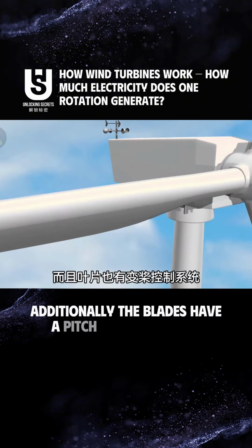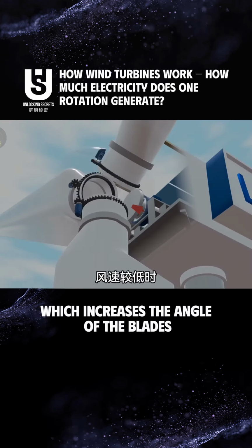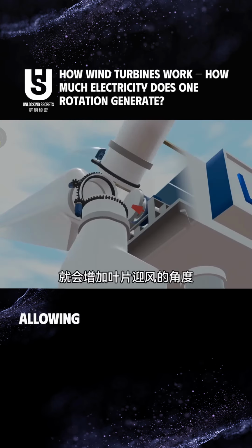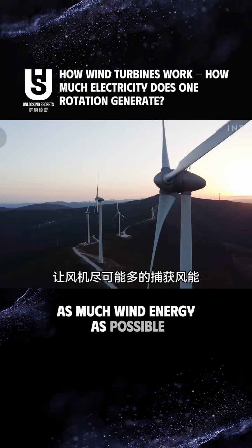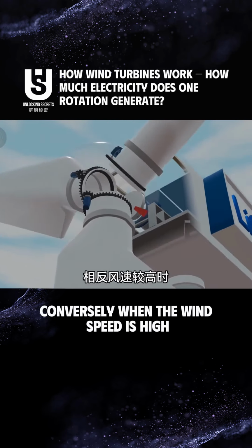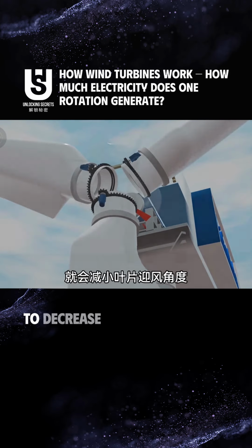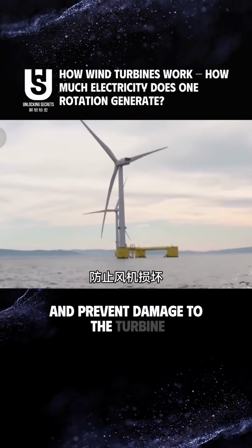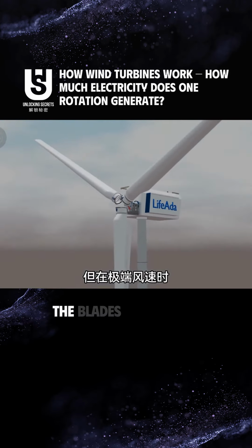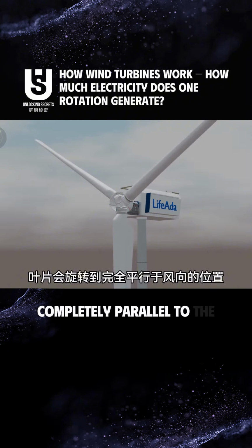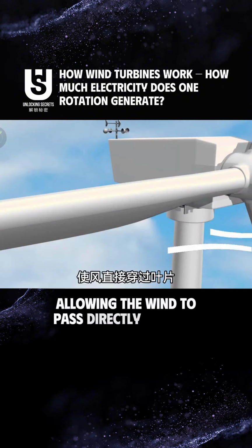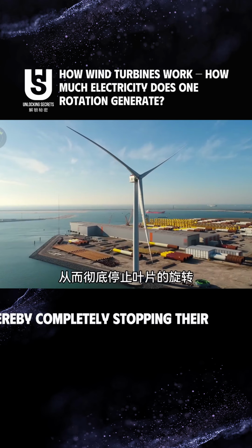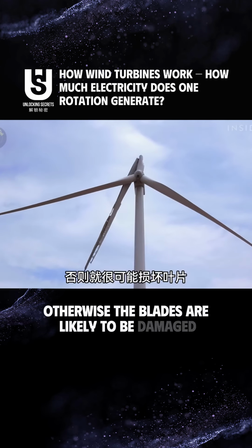Additionally, the blades have a pitch control system, which increases the angle of the blades facing the wind when the wind speed is low, allowing the turbine to capture as much wind energy as possible. Conversely, when the wind speed is high, the angle of the blades facing the wind is reduced to decrease the rotation speed and prevent damage to the turbine. However, in extreme wind speeds, the blades will rotate to a position completely parallel to the wind direction, allowing the wind to pass directly through the blades, thereby completely stopping their rotation. Otherwise, the blades are likely to be damaged.